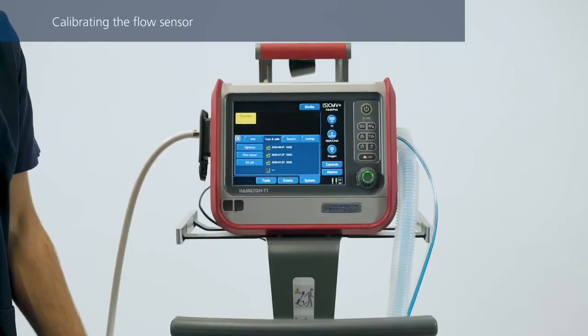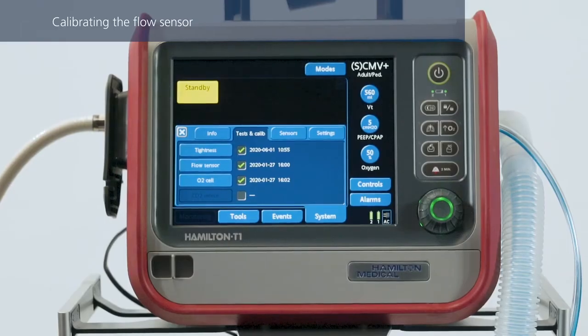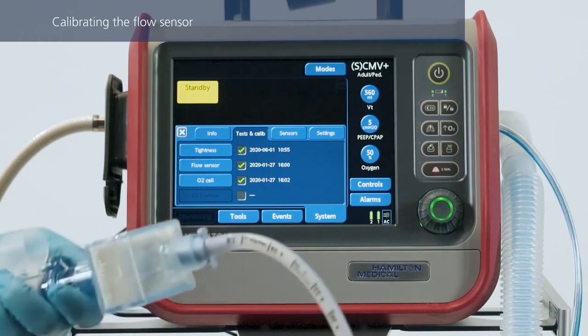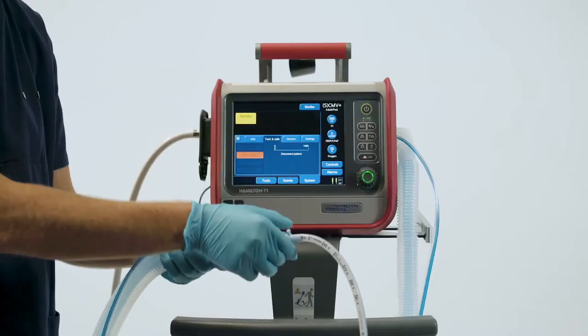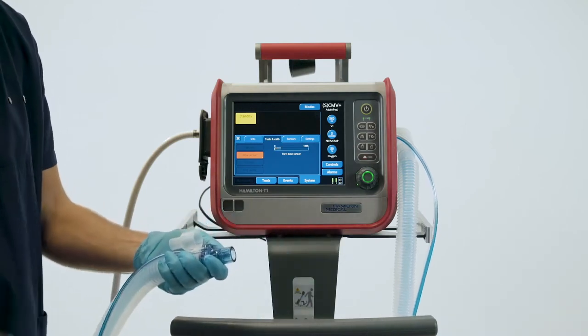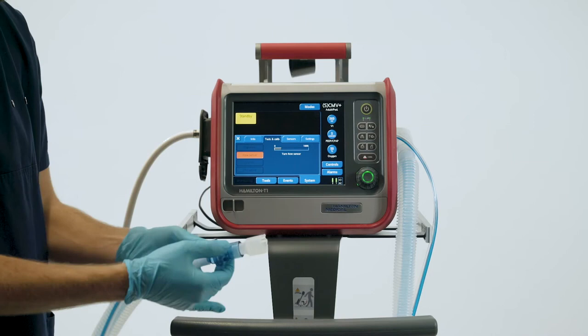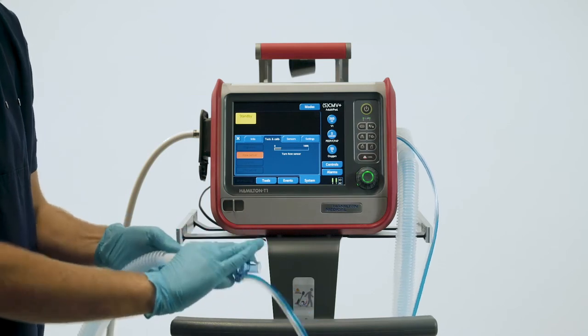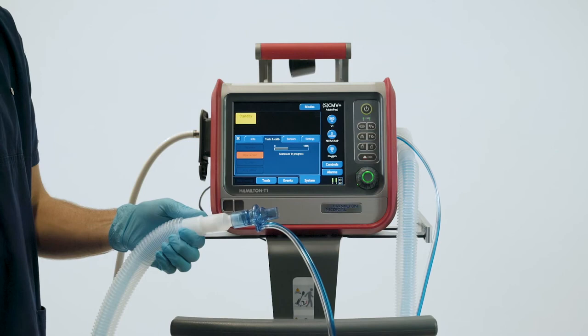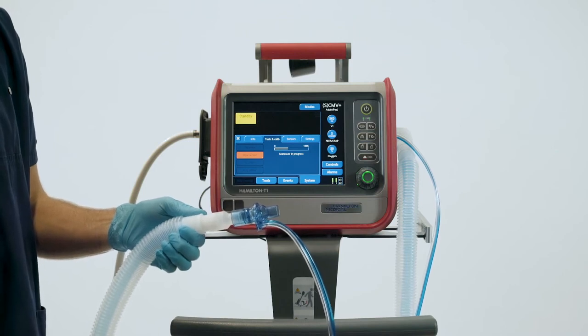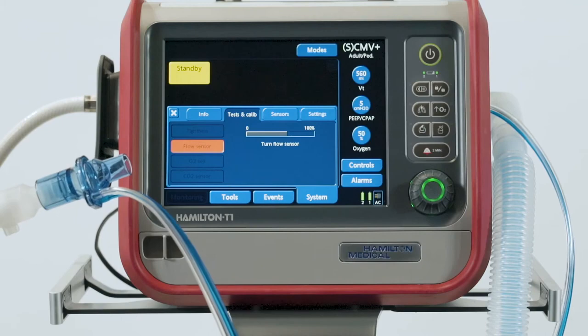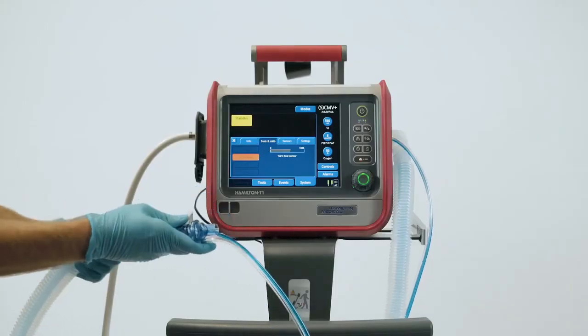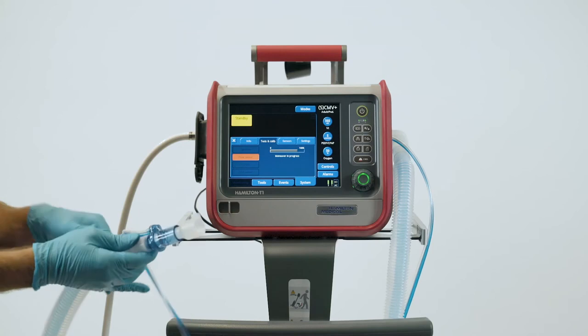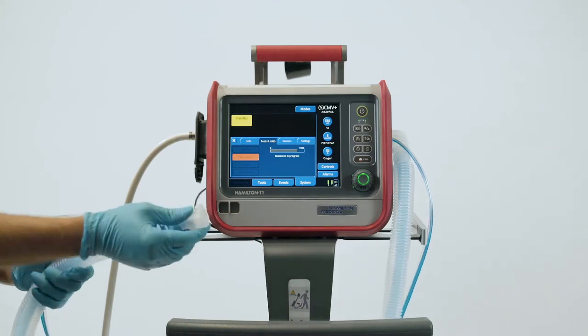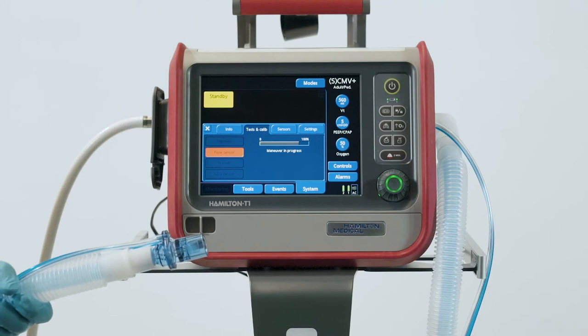To calibrate the flow sensor, choose this function and then follow the instructions on the ventilator. When the message saying "Disconnect patient" appears, you should disconnect the test lung and then attach the adapter to the flow sensor. When you see the message "Turn the flow sensor," flip the flow sensor around. Then wait and flip the flow sensor back to its starting position again. Once you've done that, you can disconnect the adapter from the flow sensor. When calibration has been completed successfully, a green check mark will appear in the box.